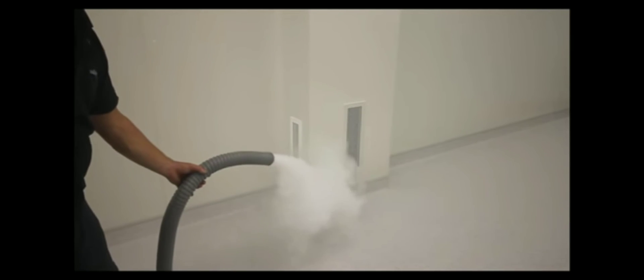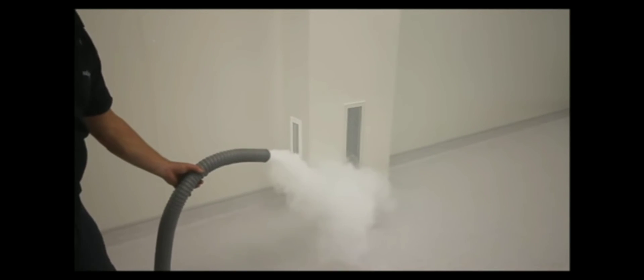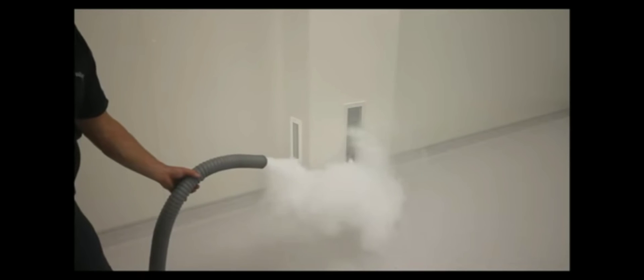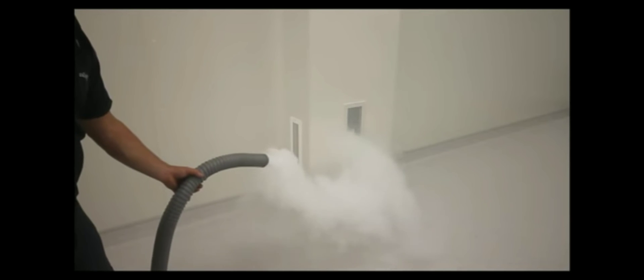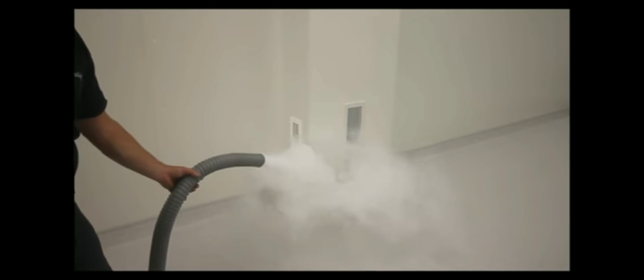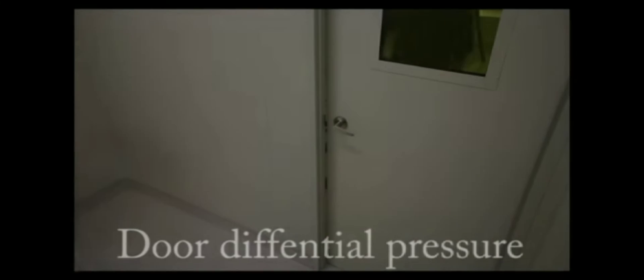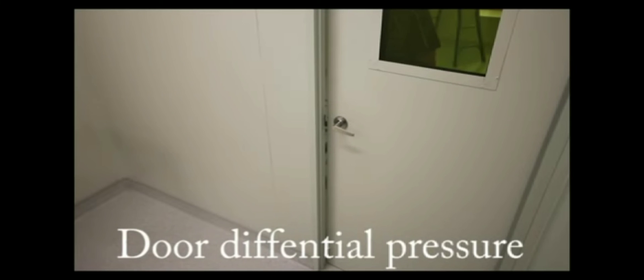It is also very important to use a smoke with a large enough particle size to get caught in the primary filters as not to affect the secondary or HEPA filters with the density of the smoke in the filter itself.